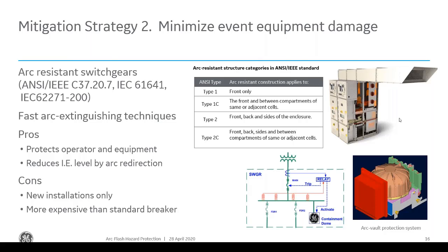The cons of this, as I mentioned, is that it is very costly compared to just buying a standard breaker and associated switchgear. It can only be done for new installations; it is probably very difficult, if not impossible, to upgrade existing switchgear to be arc resistant. But as I mentioned, it's one of the most effective techniques for mitigating arc flash and the arc flash incident energy, and hence making it safe for personnel to work in and around the switchgear.